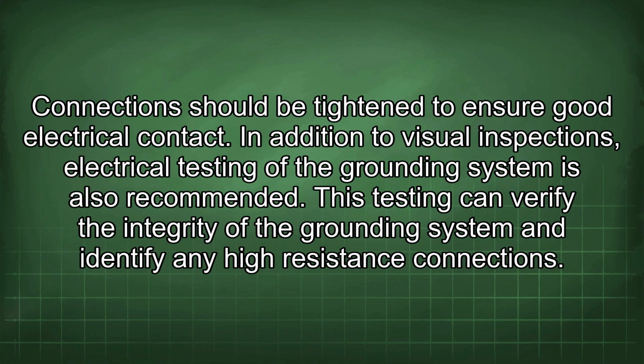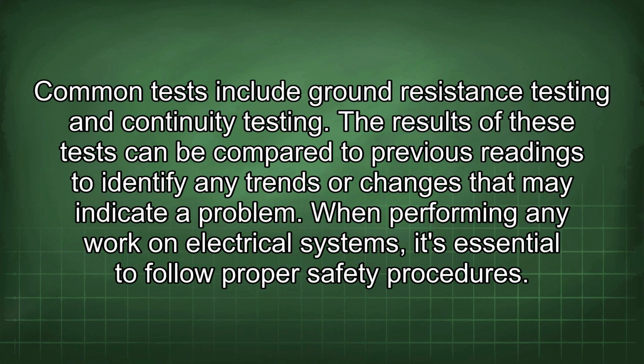In addition to visual inspections, electrical testing of the grounding system is also recommended. This testing can verify the integrity of the grounding system and identify any high resistance connections. Common tests include ground resistance testing and continuity testing. The results of these tests can be compared to previous readings to identify any trends or changes that may indicate a problem.